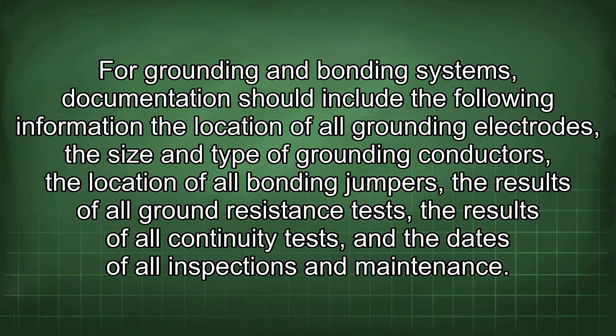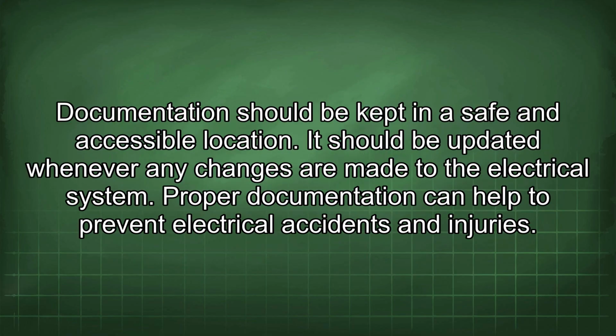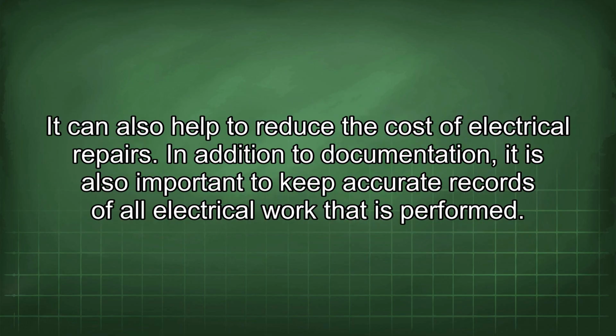For grounding and bonding systems, documentation should include the following information: the location of all grounding electrodes, the size and type of grounding conductors, the location of all bonding jumpers, the results of all ground resistance tests, the results of all continuity tests, and the dates of all inspections and maintenance. Documentation should be kept in a safe and accessible location. It should be updated whenever any changes are made to the electrical system. Proper documentation can help to prevent electrical accidents and injuries. It can also help to reduce the cost of electrical repairs.